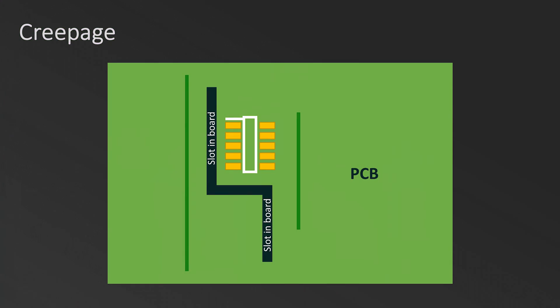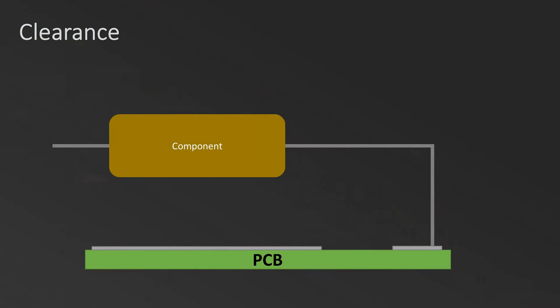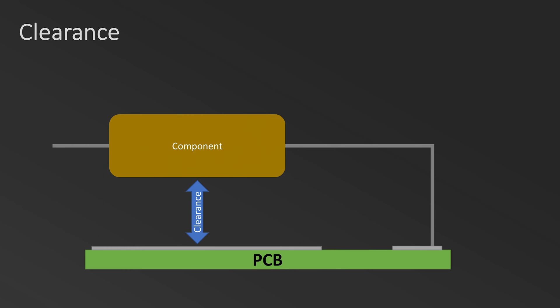Creepage and clearance are two ways to measure how far apart something is electrically. Creepage distance is a measure of how far apart two objects are across the surface of a circuit board. This can involve current creeping around corners, around the board edge, from top layer to bottom, reaching around routed slots — hence the name creepage. Clearance distance is a simpler measure: it's how far apart two conductive objects are with air between them, or an air gap — usually just the shortest straight-line distance since electricity takes the path of least resistance.